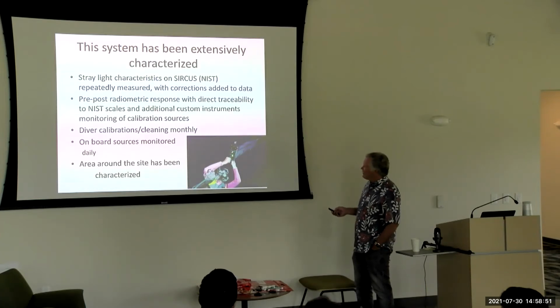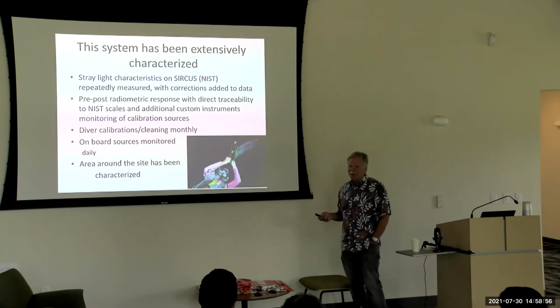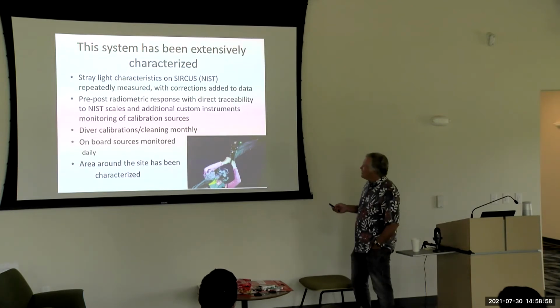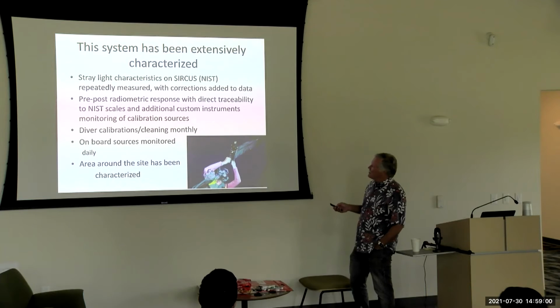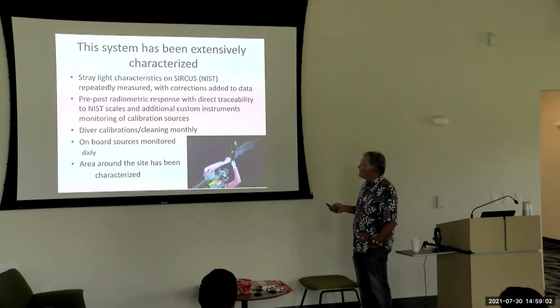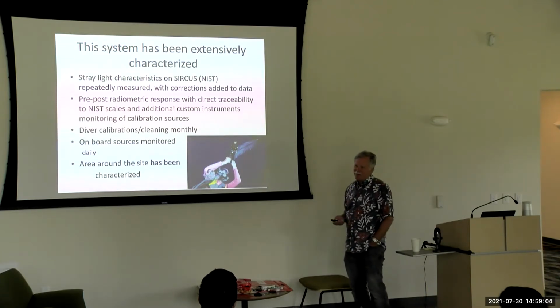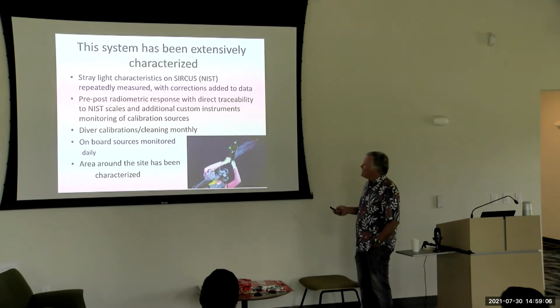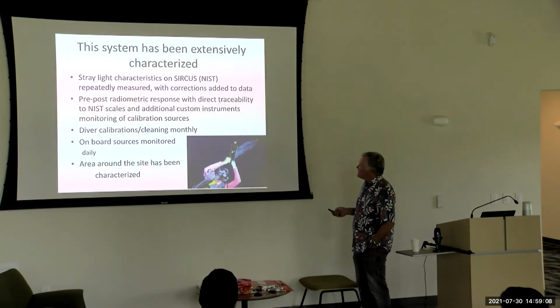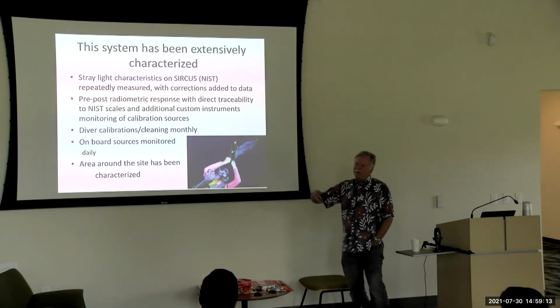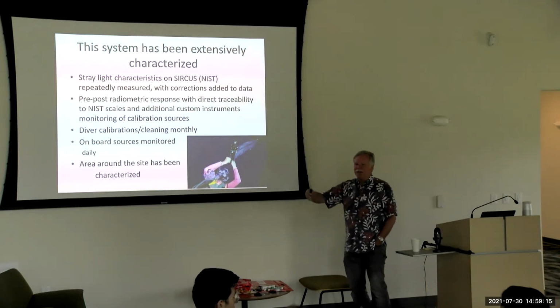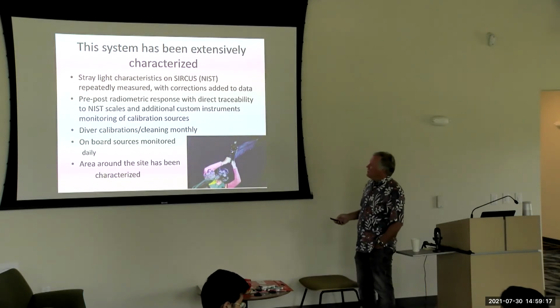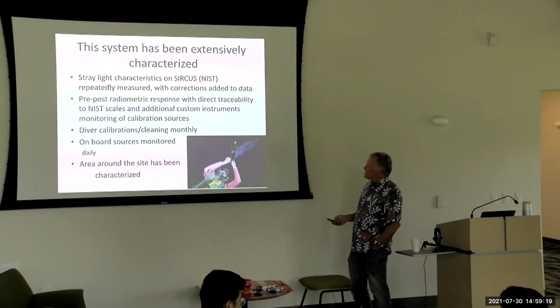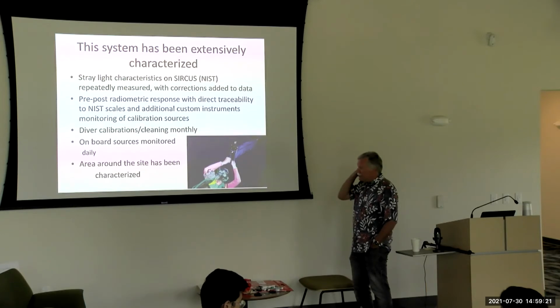We have diver calibrations monthly and cleaning. I'll tell you the truth, the calibrations aren't that good. We're measuring things, we want calibrations to 2%. It's really hard to do that on a diver. But the diver does do monthly, and we'll do the calibration. It gives us, if something drastic happens, a timing for it. We have onboard calibration sources that are monitored every day.